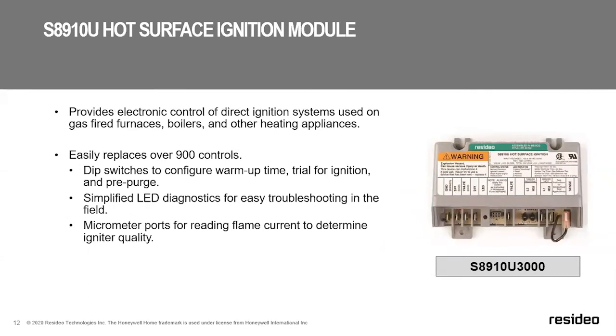Another universal module that we have is for hot surface ignition. And this one is a beast. This one module, the S8910U 3000 module, covers over 900 competitive models. One on your truck, practically everything you can come across, that one model will replace it, which is a fantastic thing. It also has LEDs for diagnostics and micrometer ports to determine your flame current. It uses dip switches depending on the configuration for the particular control that you're replacing.